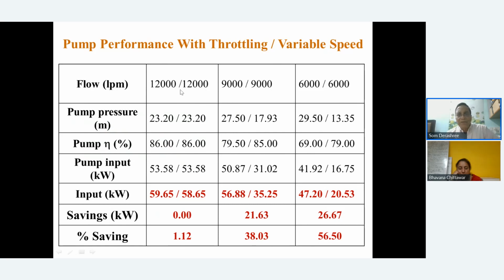So from 12,000 to 9,000, you see the pressure will increase when you are throttling, because the back pressure of the valve has come onto the pump. And if you further reduce, these are the two: this is the throttling and this is the VFD. If you do VFD, the head requirement will be lower because it falls as the square of the speed, as per the affinity law. We'll come to that subsequently. The pump efficiency, which was 86%, has come down to 79% when you are throttling the valve. In VFD, it is almost the same, 85%, because you have shifted the curve below. And the pump kilowatts, etc., and the saving will be shown here.